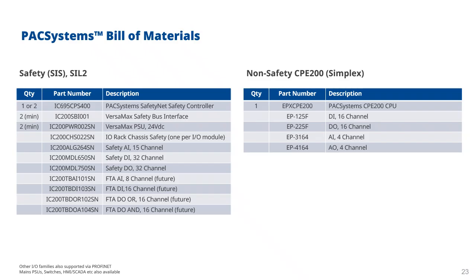For the safety bus interface, it's IC200 SBI 001, and you're always going to need at least two of those. The safety bus interface requires a power supply, which is the IC200 PWR002 SN, and then you would have as many IC200 CHS022 SNs, which is your safety chassis, one I/O module for each one. And then you've got the safety I/O, the ALG264 SN, you've got the discrete inputs, MDL650 SN, and your safety discrete output, MDL750 SN. We are planning these field terminal assemblies, but currently they're not in the Emerson price list. That will be a future addition.